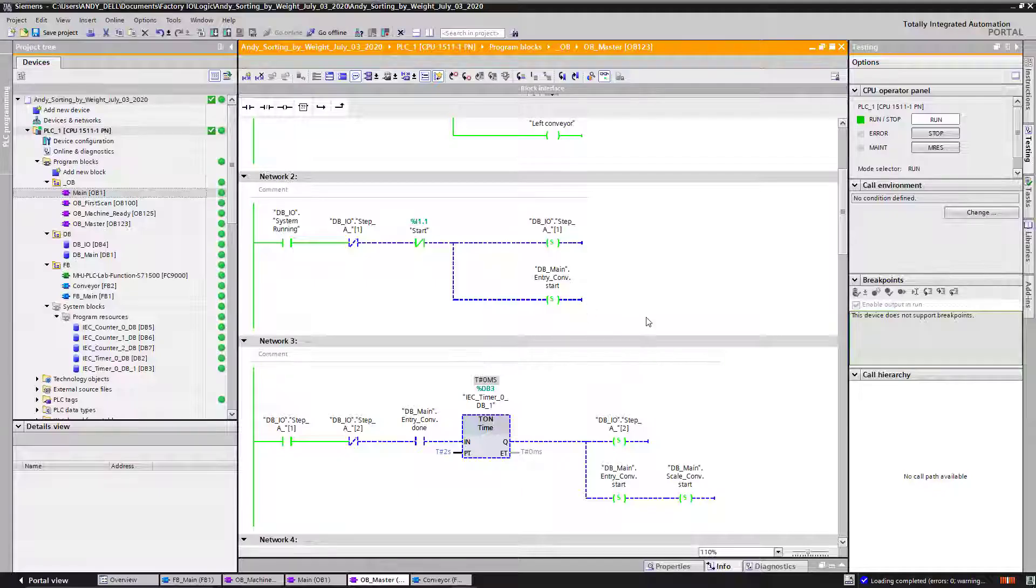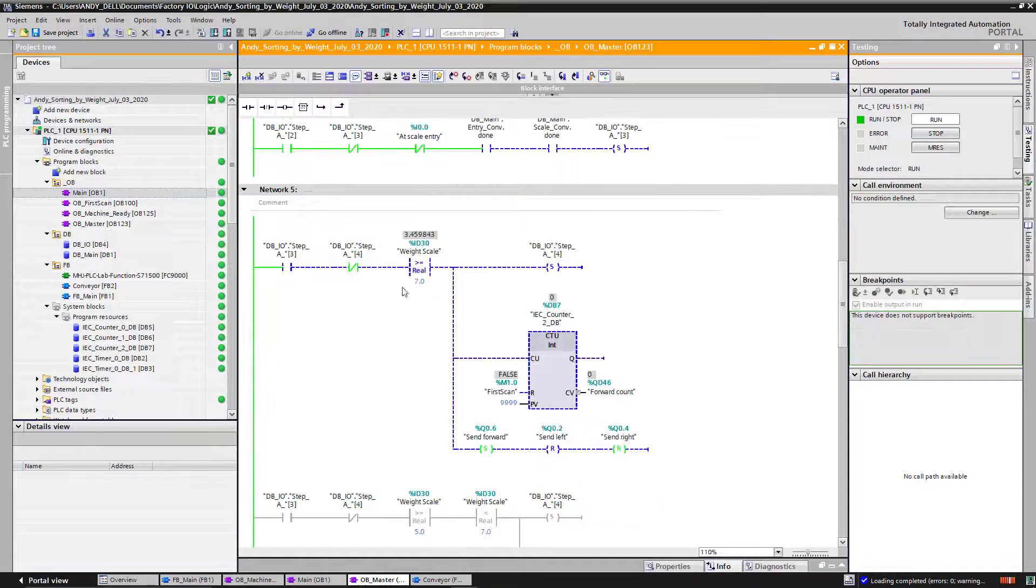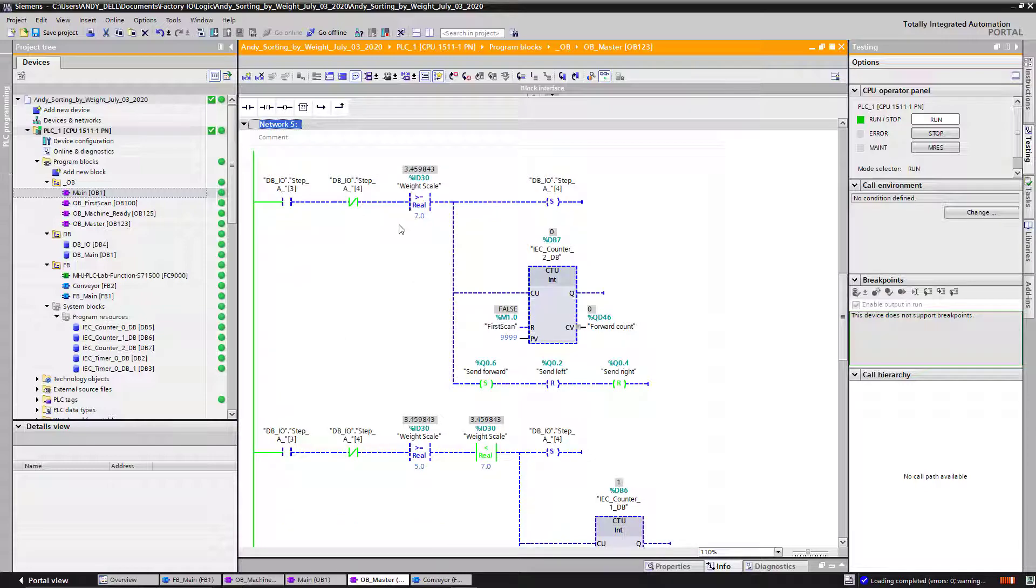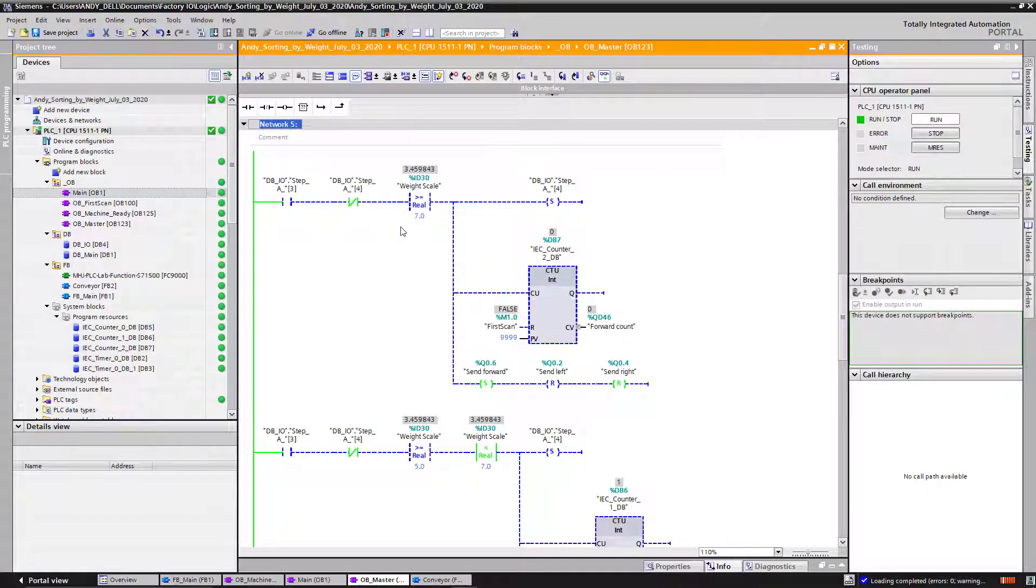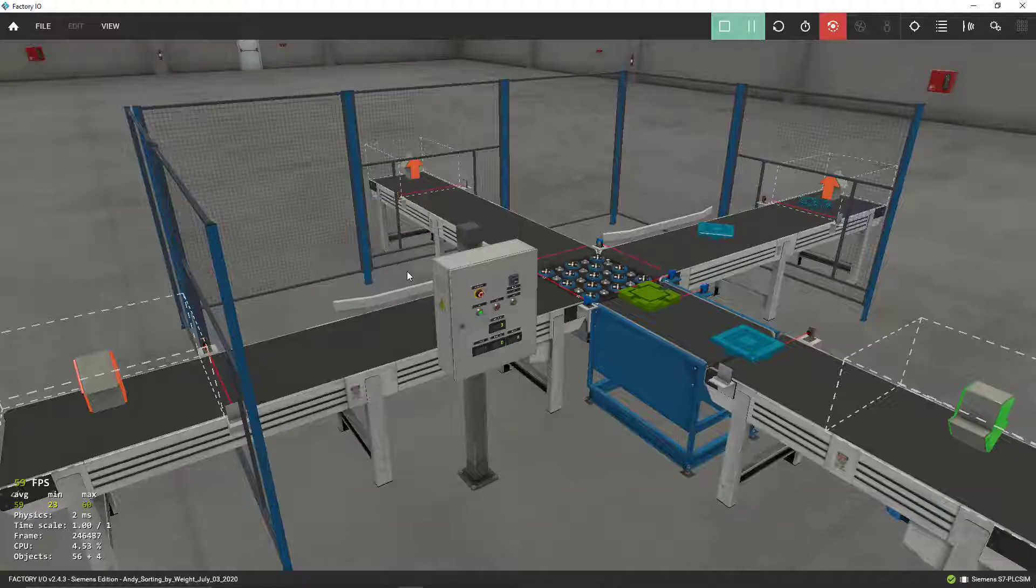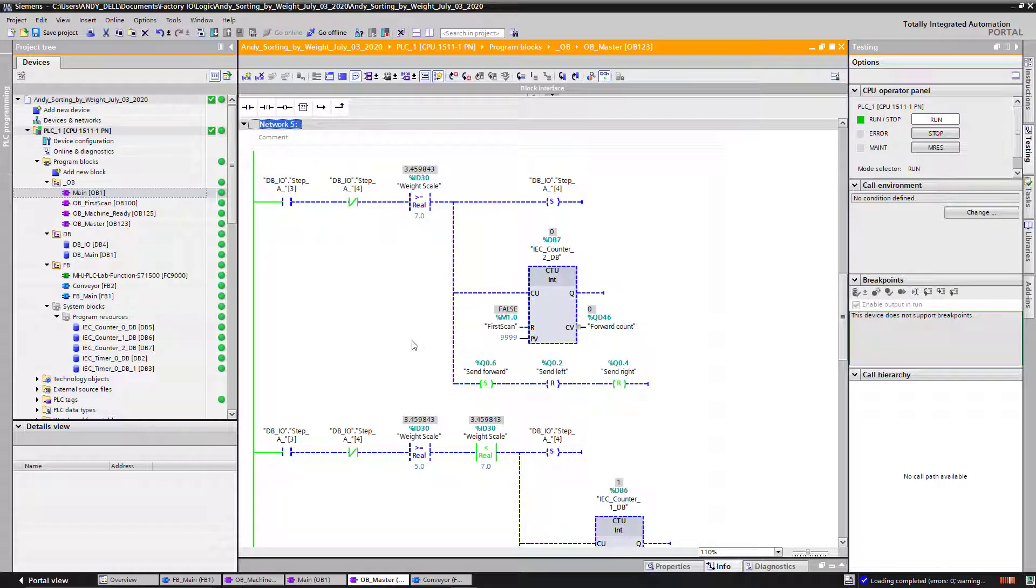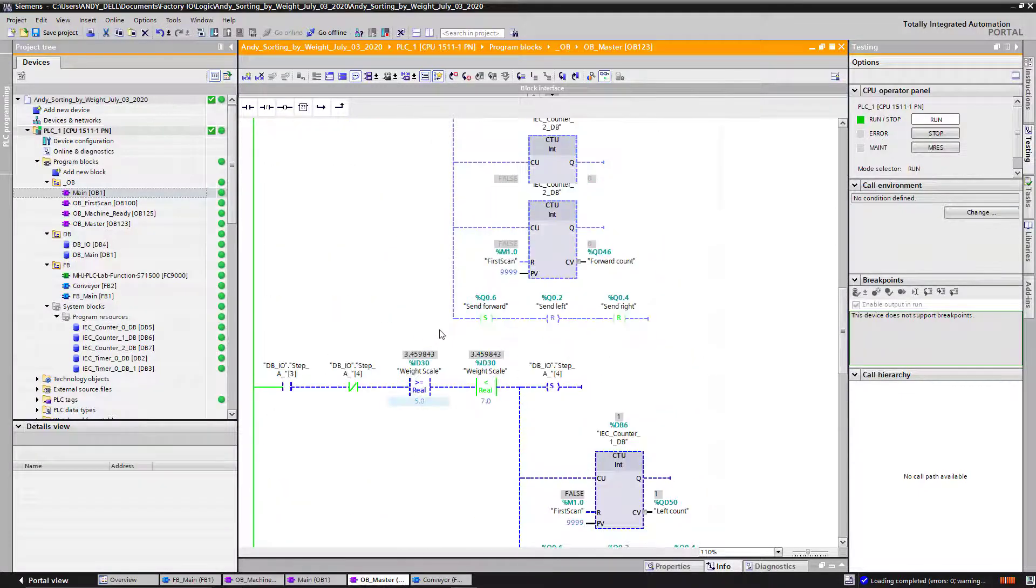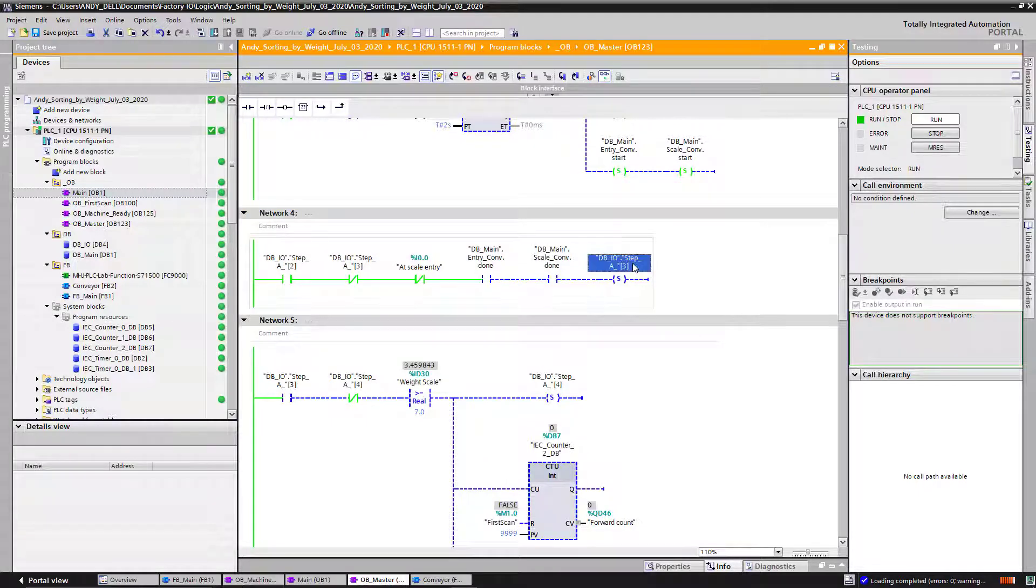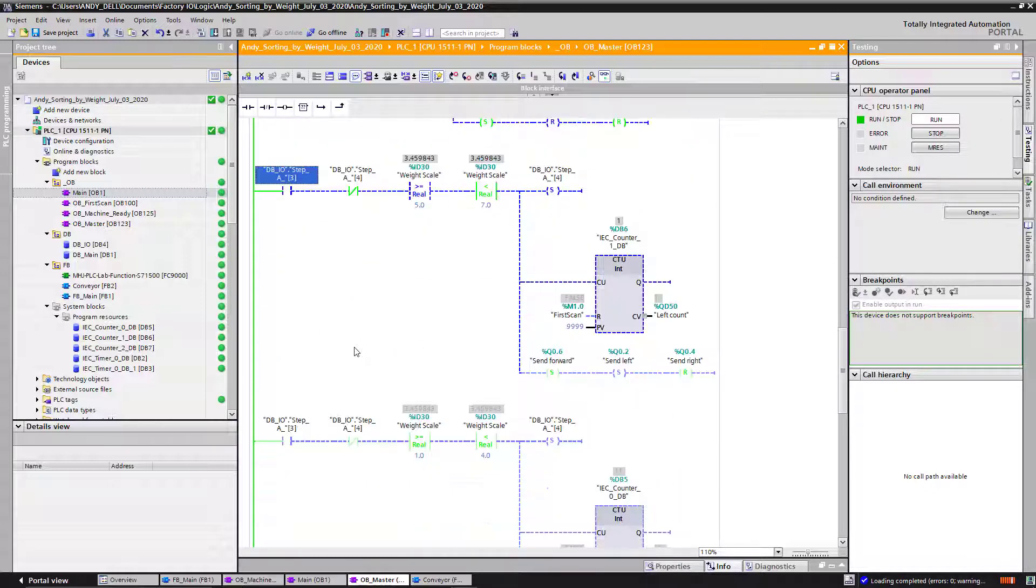Okay, there is a piece of code that I use over here on network 5. This code is the one making the decision as to how much each box weighs and whether I should go forward or send it to my left or send it to my right. This is where I make that decision. If you see this one over here on network 4, I activate my step 3, and this step 3 over here is repeated over here in these three rungs on my network 5.